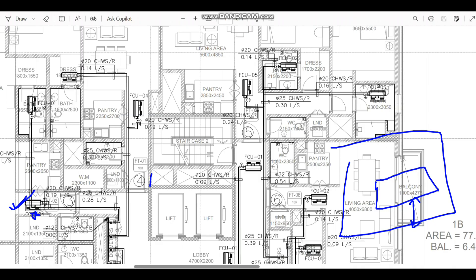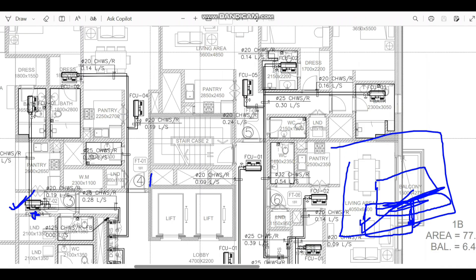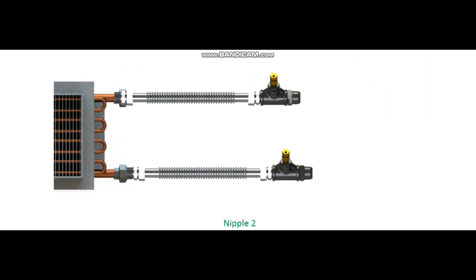Regarding FCU filter clearance: we need to open the access panel in the ceiling, go inside, and remove the filter. If you cannot provide adequate space on the back side, when ordering materials make sure the FCU filter arrangement can be accessed from the bottom of the FCU — that option is also available from manufacturers. It is not a rule that the filter must be on the back side; you can request a bottom-filter configuration. The recommendation is to keep at least 500mm behind the FCU, and proper access panel provision ensures good engineering practice.